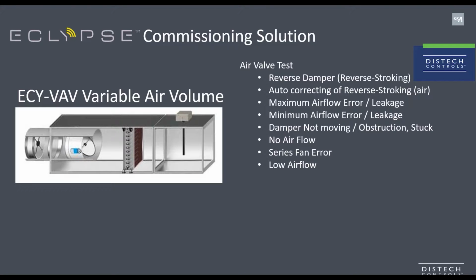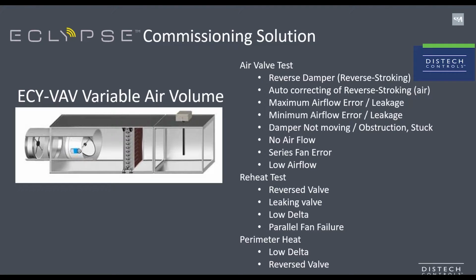Not only would you be provided with operational information, the ECLYPSE Edge Analytics can automatically correct the damper direction when reversed. Also, provided that your system is equipped with a discharge temperature sensor, you can also run tests and generate reports on the operation of your equipment. The system will automatically detect if your reheat valves are reversed, leaking, or if your coils are not delivering enough heat. This test will also provide you with information on the proper operation of your parallel fan. If your system is equipped with either heating radiator or electric baseboard, you'll also be able to detect reverse valves or low temperature output failure.